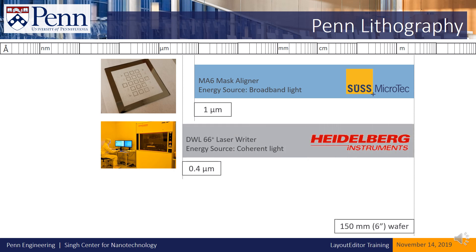If you'd like to make photo masks for use in the mask aligner, or print features down to around 400 nm in minimum feature size, you should consider using the Heidelberg DWL66PLUS LaserWriter. This tool writes on samples directly, so exposures take longer than on the mask aligner, but it's capable of printing smaller features.